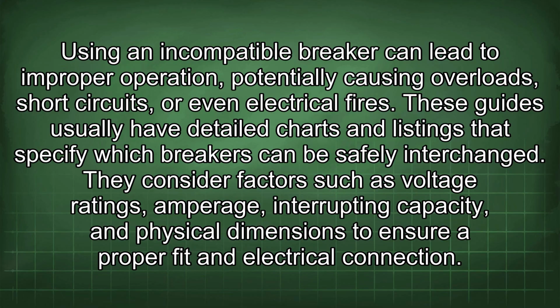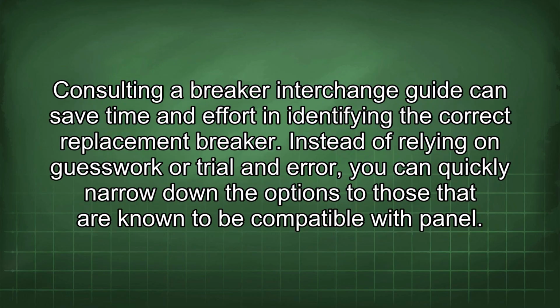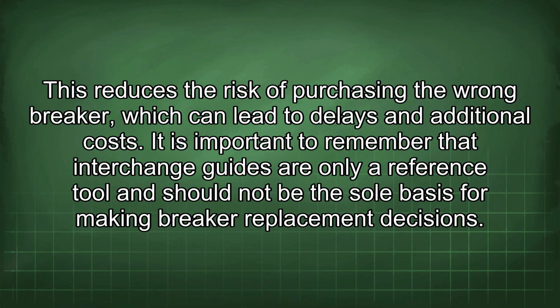These guides usually have detailed charts and listings that specify which breakers can be safely interchanged. They consider factors such as voltage ratings, amperage, interrupting capacity, and physical dimensions to ensure a proper fit and electrical connection. Consulting a breaker interchange guide can save time and effort in identifying the correct replacement breaker. Instead of relying on guesswork or trial and error, you can quickly narrow down the options to those that are known to be compatible with the panel. This reduces the risk of purchasing the wrong breaker, which can lead to delays and additional costs.